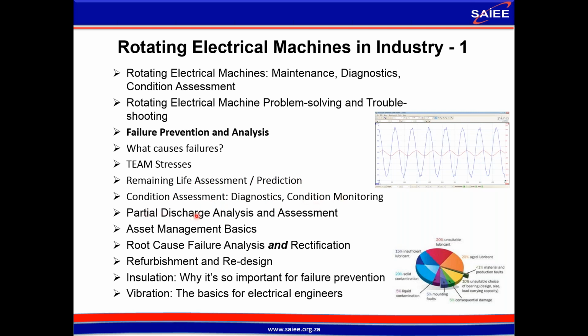Then the specific testing we look at, partial discharge analysis. We look at asset management basics, root cause failure analysis, and rectification. That's very important. It's one thing to identify the root cause of a failure and another thing to rectify it. And leading on from rectification is refurbishment and redesign. Those of you in the maintenance and repair industry will realize that sometimes the repair of a failed motor involves a redesign, even of more modern machines. Why is insulation so important for failure prevention? And then the second one on that is bearings, because they're the two most common failures.